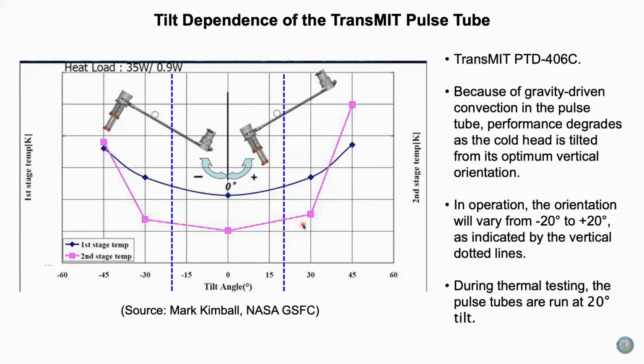So the magenta line here is the temperature of the colder second stage. It's supposed to be colder anyway, as a function of tilt angle from the vertical. The blue line here is the temperature as a function of tilt angle of the first stage. And you can see there is some dependence. It's not terrible between minus 20 and 20, which is what it has to cover. You get out beyond 30 degrees, it kind of goes nuts. You don't want to go out there.